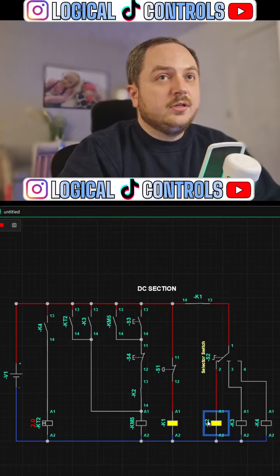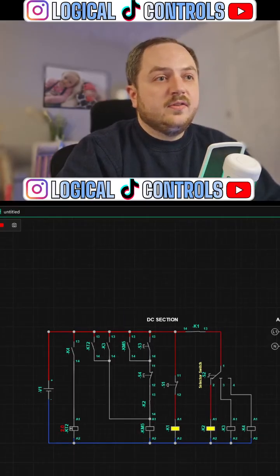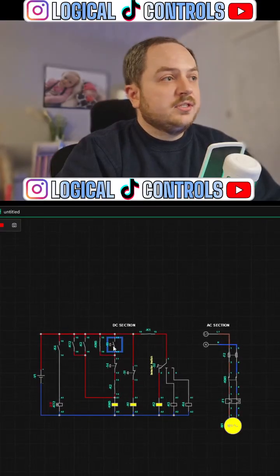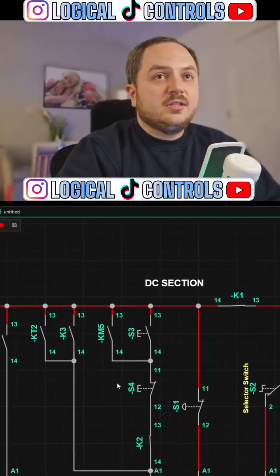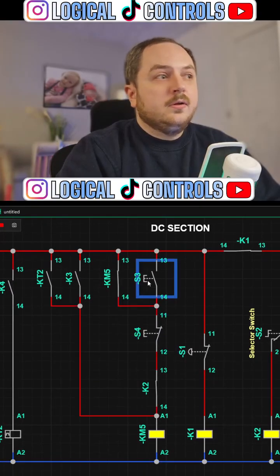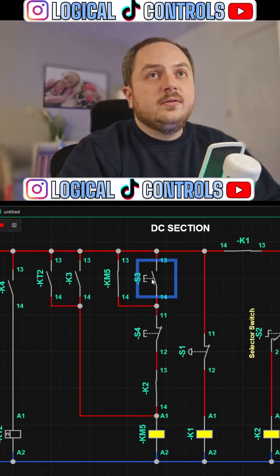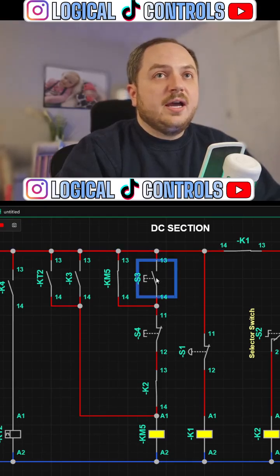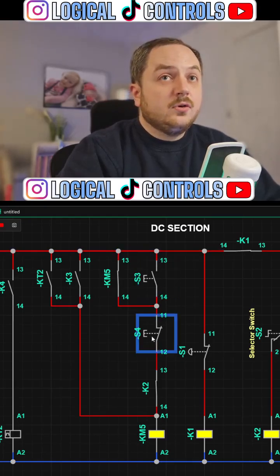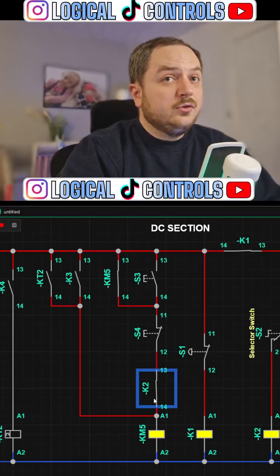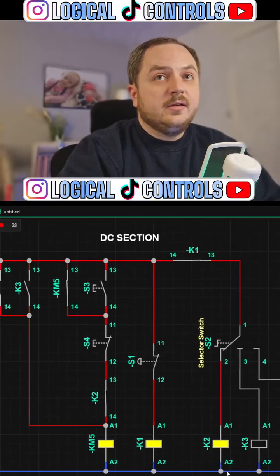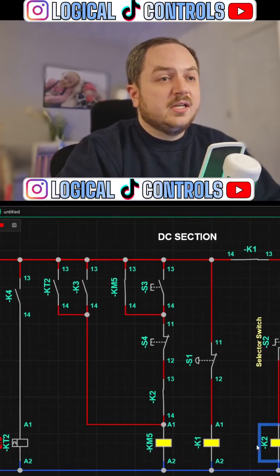So we've got control of the start and the stop. If I just zoom out a little bit so you can all see, I press start, the motor starts. I press stop, the motor stops. Whenever I press the start button, I think you can see that all right, it's putting a supply down through S3, through S4 because that's normally closed, through K2 because that's already energized by being in the manual mode. That's basically our mode position, manual mode position.